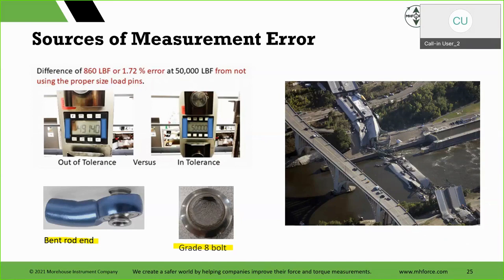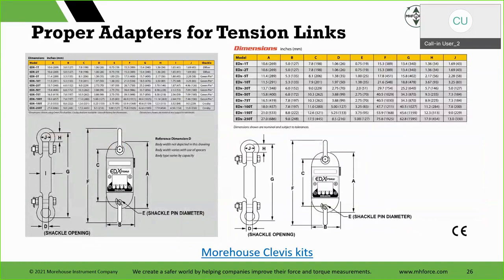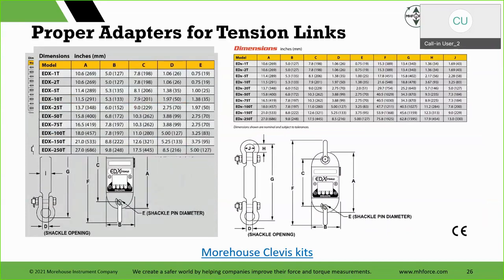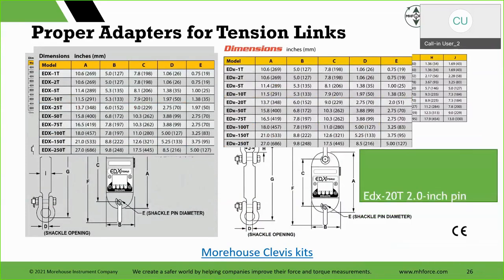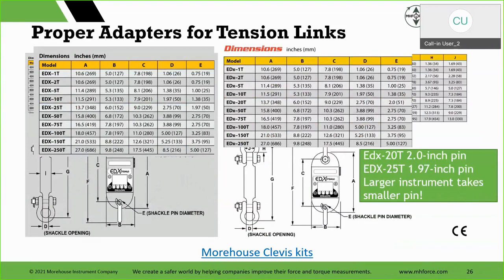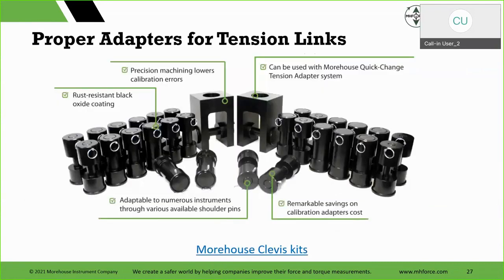If we examine the safety concerns with using older adapters and we discuss some of those error sources, we can start seeing ways to solve them. Here are proper adapters for tension links, right? We have clevis kits, like I said, that'll do this. But if you look at the sheets, it says this one uses a 2-inch pin and this one uses a 1.97-inch pin. One, that's actually a 50-millimeter pin. There's going to be a difference. A lot of people are going to say, that's minute, I can just use the same pin. We've done it. Some of the times you're out of tolerance because you're using a too small or too large pin. So it's really important for you as a cal lab to replicate that.